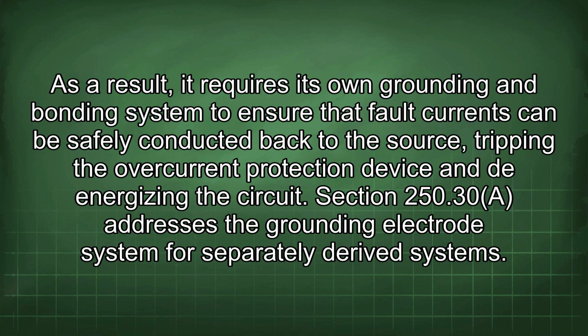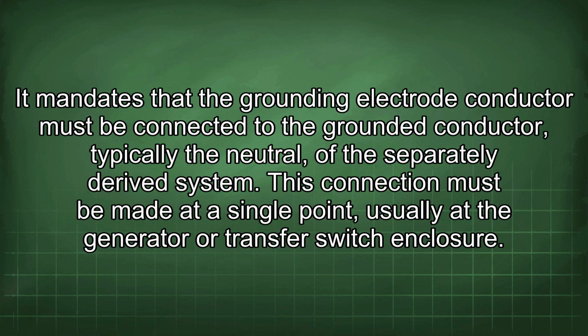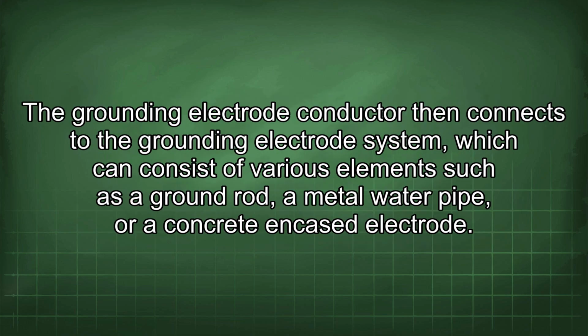Section 250.30 addresses the grounding electrode system for separately derived systems. It mandates that the grounding electrode conductor must be connected to the grounded conductor, typically the neutral, of the separately derived system. This connection must be made at a single point, usually at the generator or transfer switch enclosure. The grounding electrode conductor then connects to the grounding electrode system, which can consist of various elements such as a ground rod, a metal water pipe, or a concrete encased electrode.